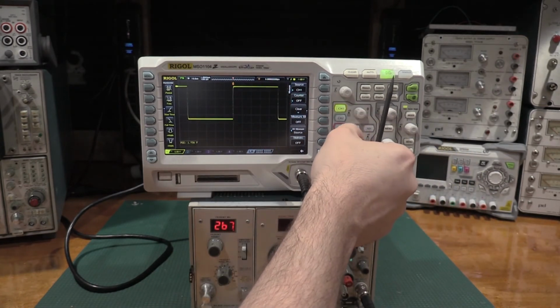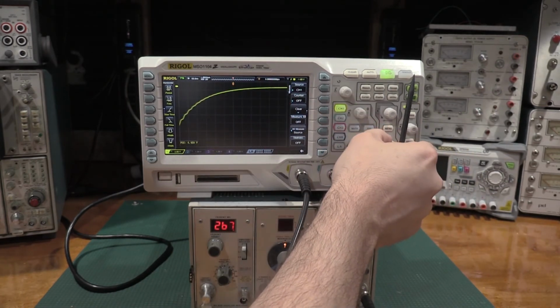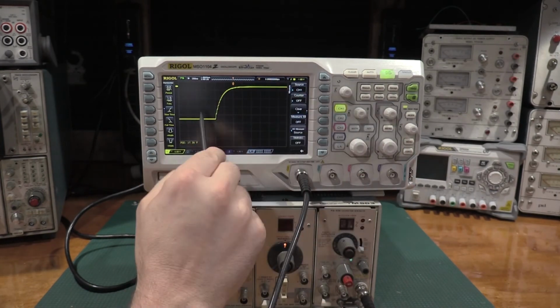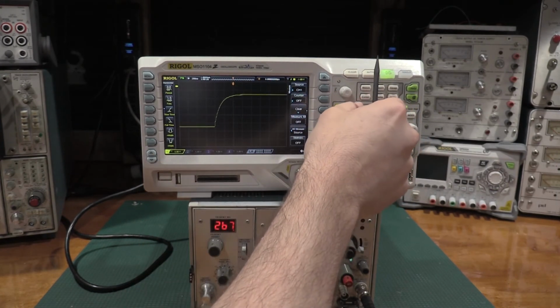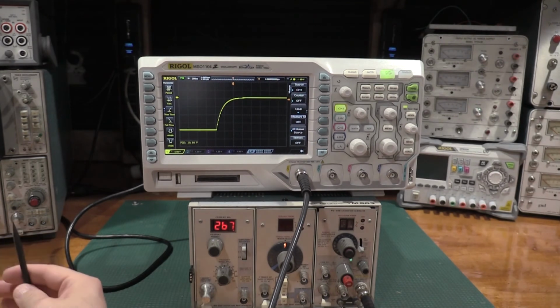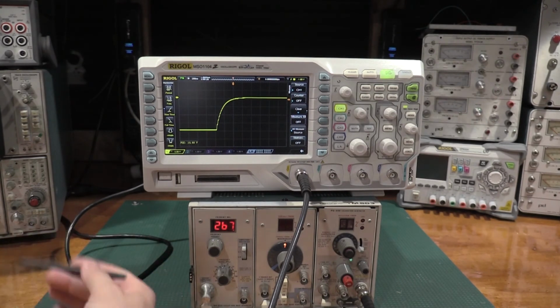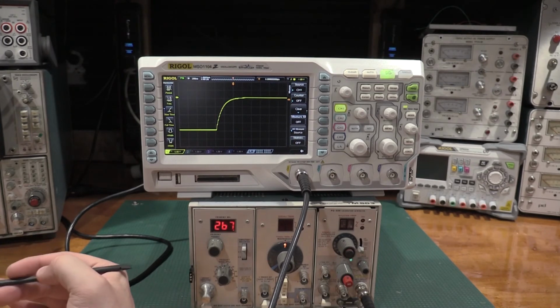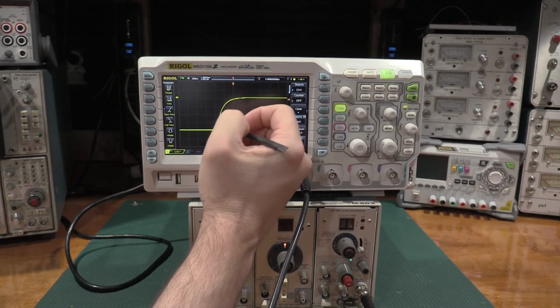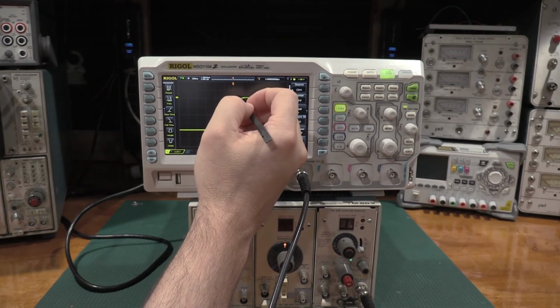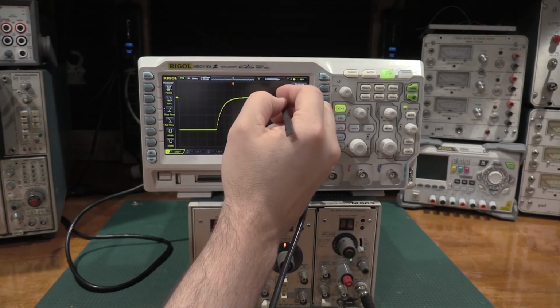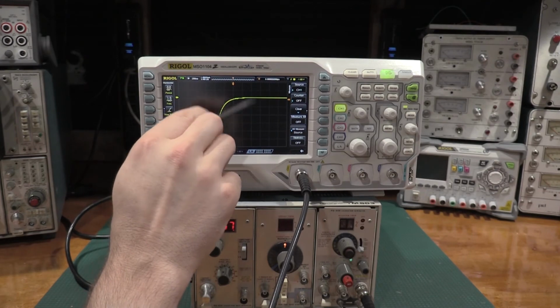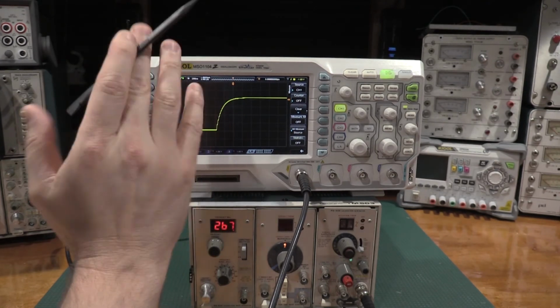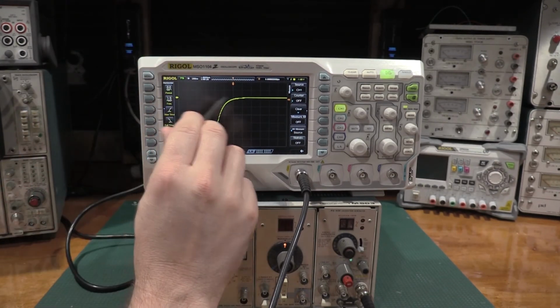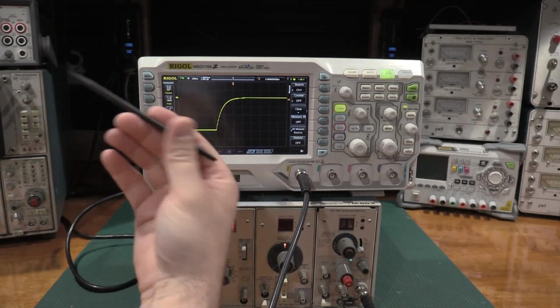If we zoom in here, we come up and we level. Why is that important? Because when we're doing the frequency compensation of the vertical amplifiers, it's important that this comes up and then settles without any ringing or anything like that coming down the waveform, because that's what we're tuning. Reasonably fast up and a flat top is necessary.